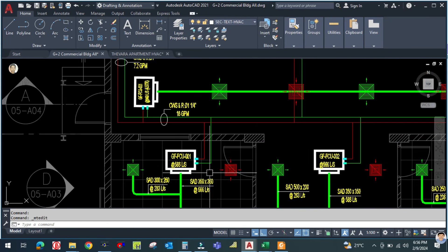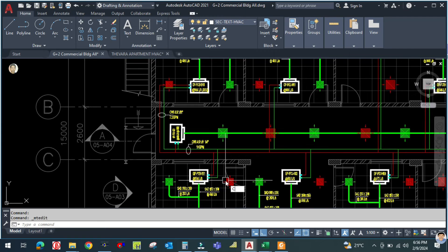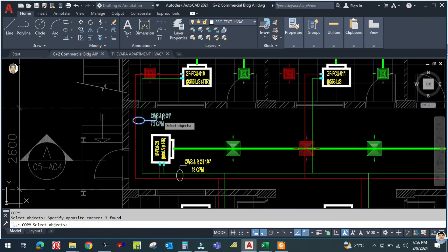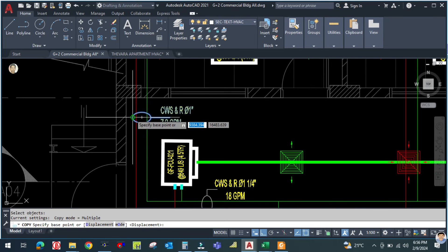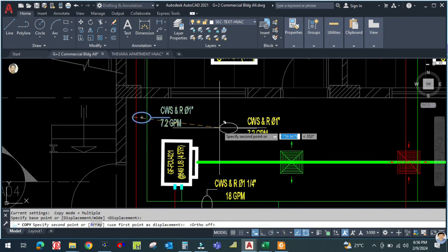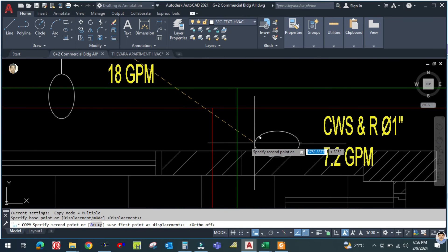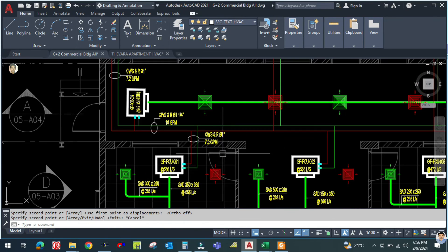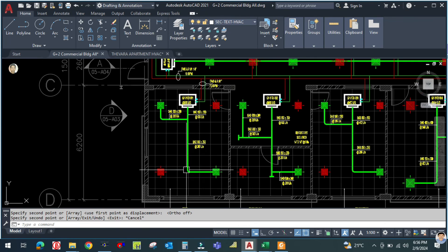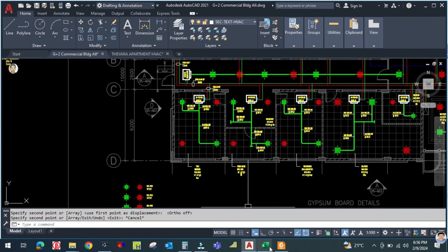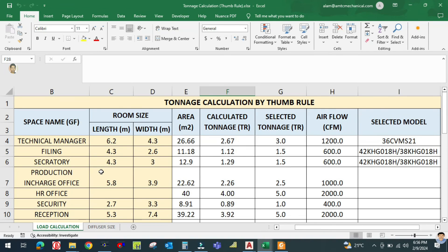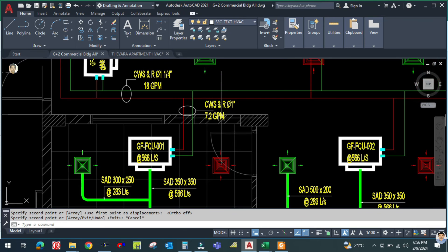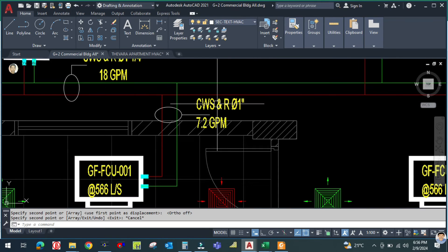Similarly for the technical manager room branch: copy the text and place it here. The machine tonnage for the technical manager room is 3 tons, so the flow rate is 7.2 GPM and the chilled water supply and return pipe size is 1 inch.